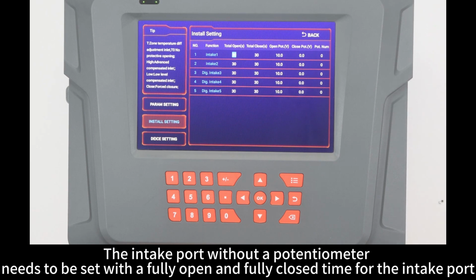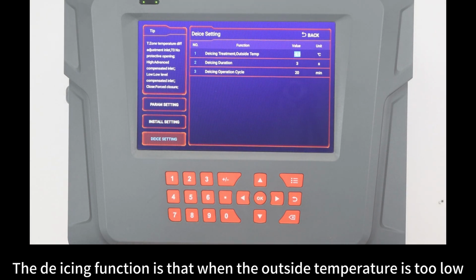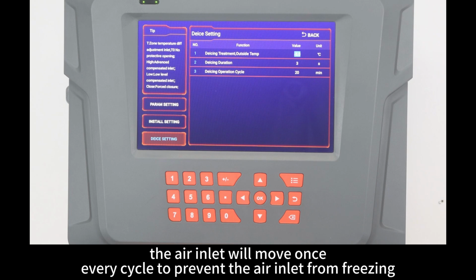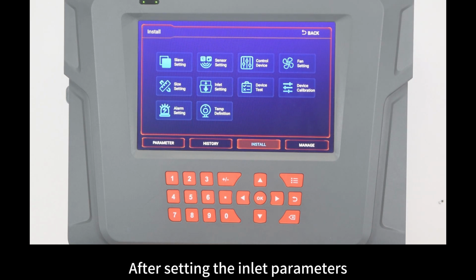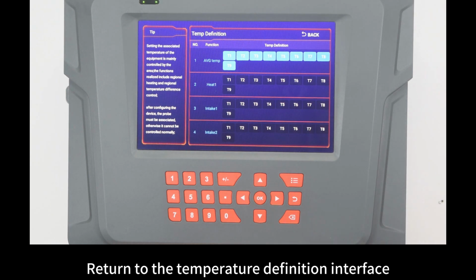The intake port without a potentiometer needs to be set with a fully open and fully closed time for the intake port. The de-icing function is that when the outside temperature is too low, the air inlet will move once every cycle to prevent the air inlet from freezing. After setting the inlet parameters, return to the temperature definition interface.